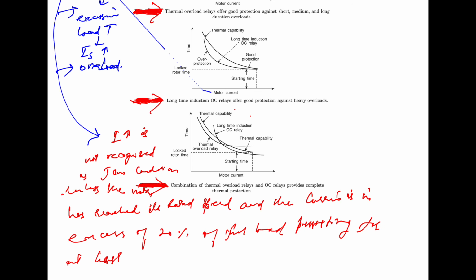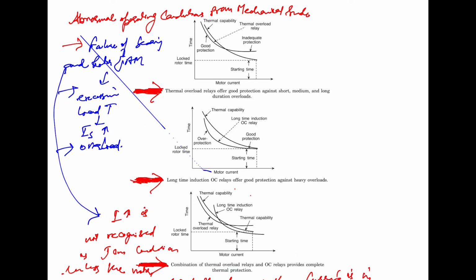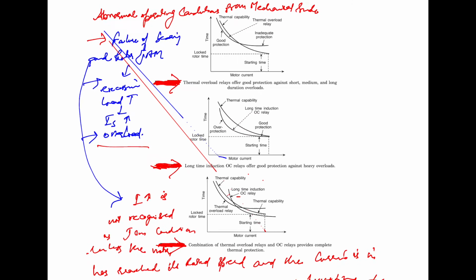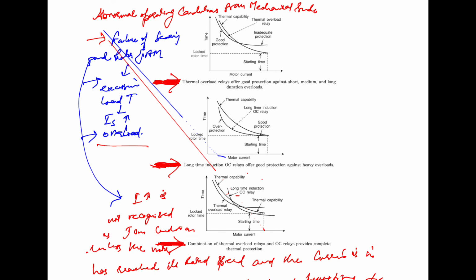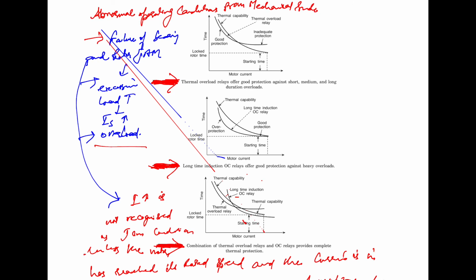For at least 2 times the locked rotor time setting. So this principle is followed. Now, next is the overload. Thermal overload relays offer good protection against short, medium and long duration overload, but may not provide protection against the heavy overload. It can provide good protection against the short, medium and long duration overloads, but may not provide the protection against the heavy overloads.